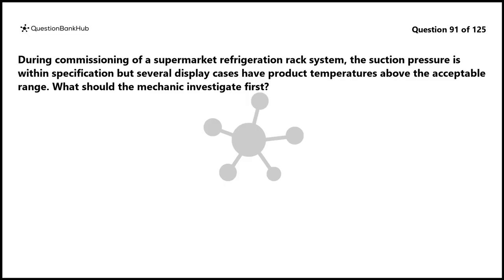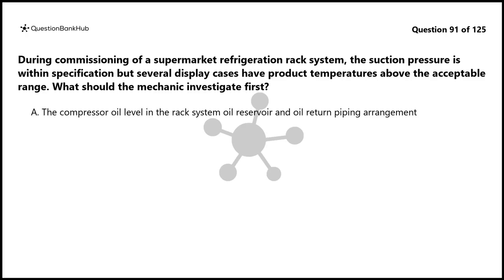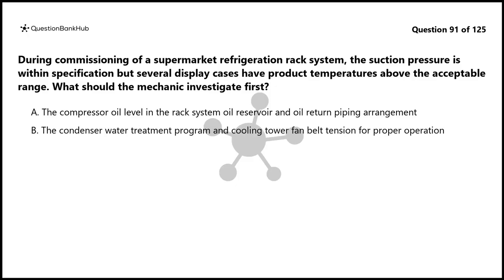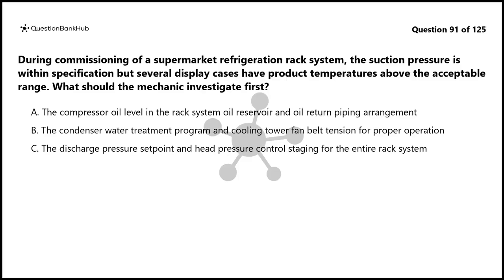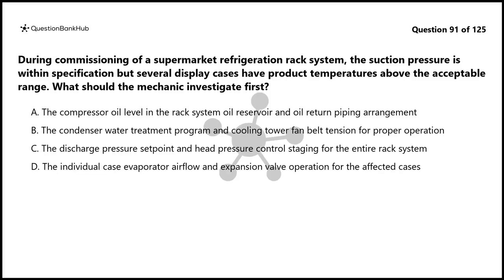Question 91. During commissioning of a supermarket refrigeration rack system, the suction pressure is within specification but several display cases have product temperatures above the acceptable range. What should the mechanic investigate first? A. The compressor oil level in the rack system oil reservoir and oil return piping arrangement. B. The condenser water treatment program and cooling tower fan belt tension for proper operation. C. The discharge pressure setpoint and head pressure control staging for the entire rack system. D. The individual case evaporator airflow and expansion valve operation for the affected cases.